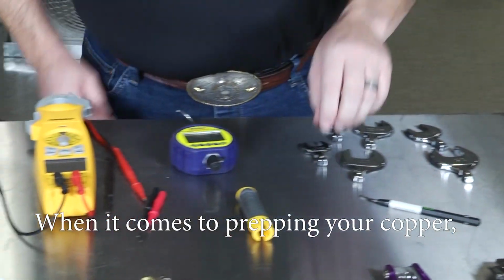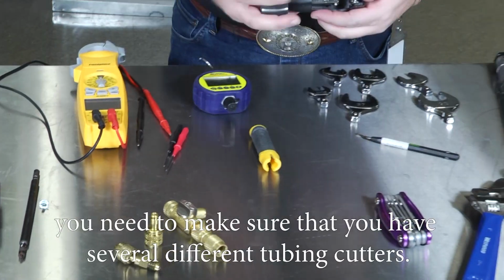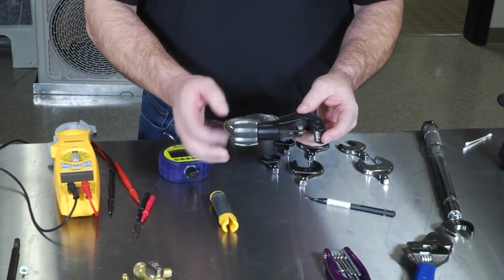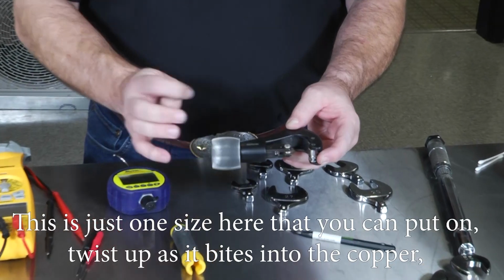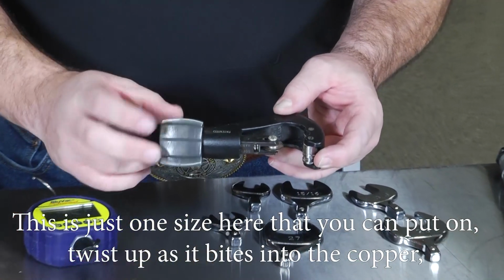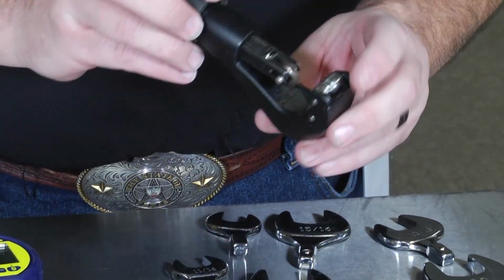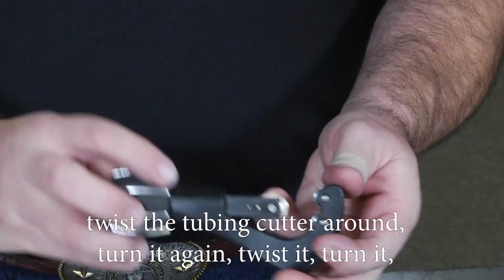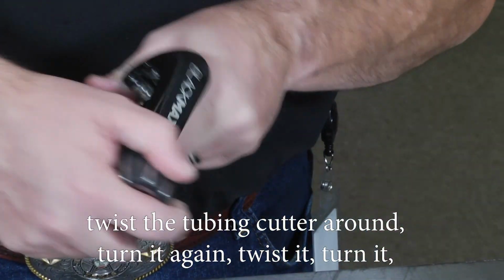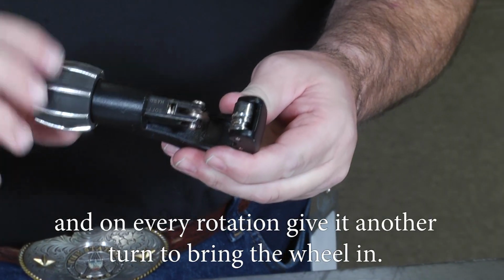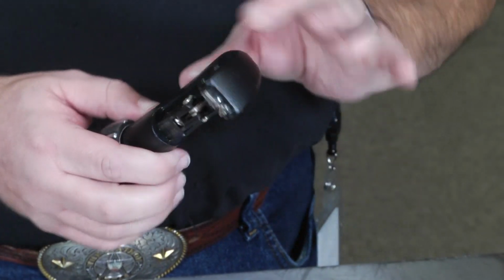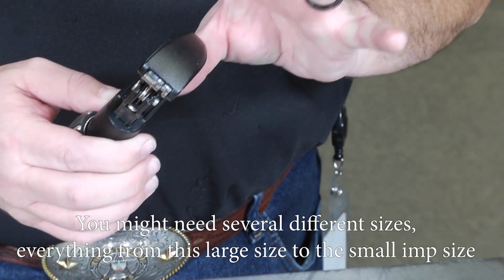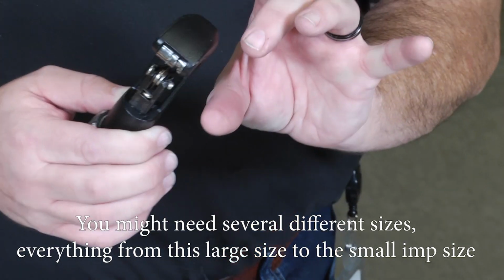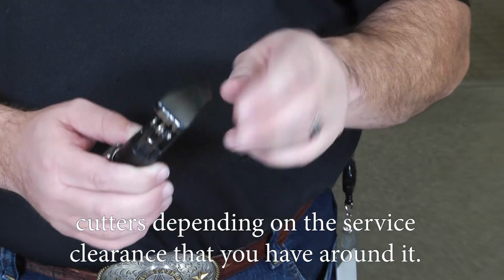When it comes to prepping your copper, you need to make sure that you have several different tubing cutters. This is just one size here that you can put on, twist up, and as it bites into the copper, twist the tubing cutter around, turn it again, and on every rotation, give it another quarter turn to bring the wheel in. You might need several different sizes, everything from this large size to the small imp size cutters, depending on the surface clearance that you have around it.